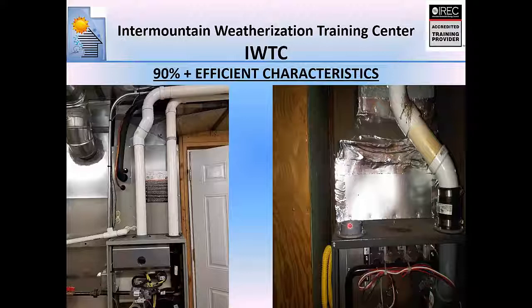Just a horrible way to do it. And then the door they put on this was a door that screwed on and sealed up, and so this thing was actually sucking its combustion air from all the holes that were left in the attic. You can see they didn't glue one of the joints properly. This is all condensation that has been dripping down, and a fine plenum install there.